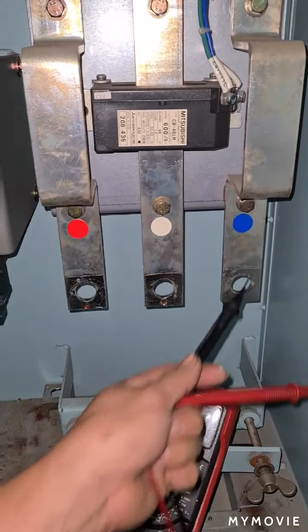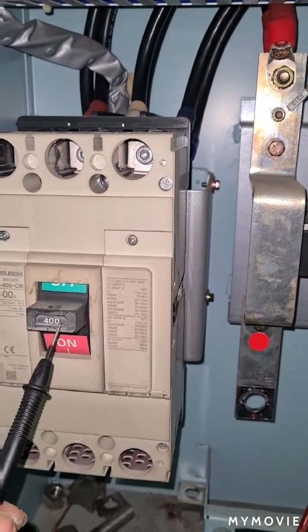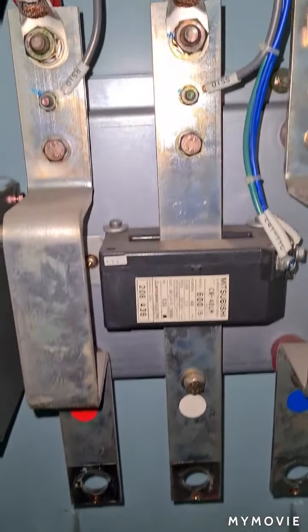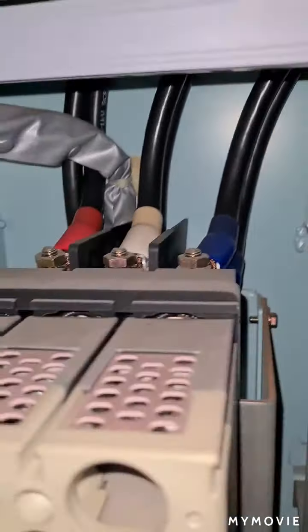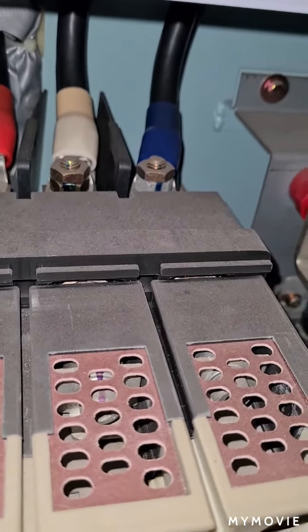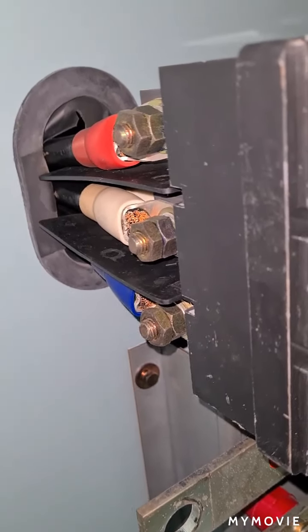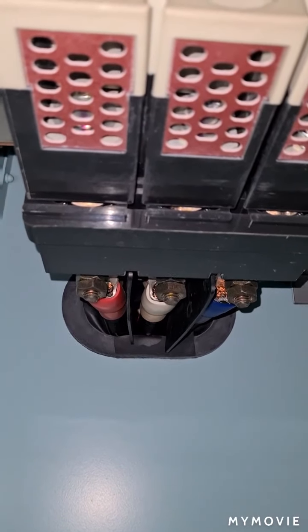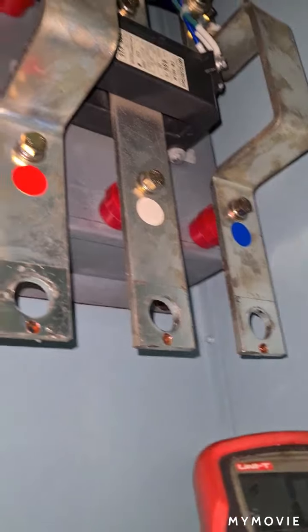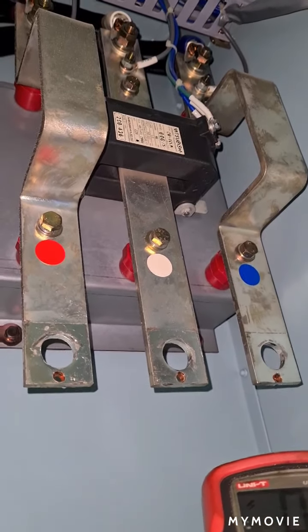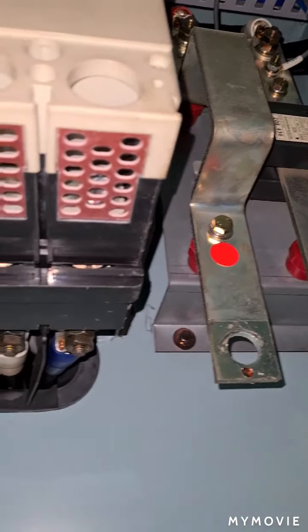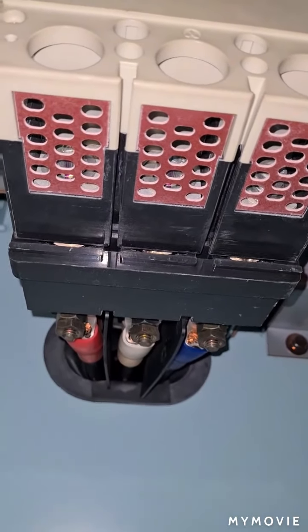Take note that this pole line 3 has no voltage. Put this switch off. As you can see here, we have a line going there, going inside, and this has the upper part portion, and this upper part portion is connected down. As you can see here, there is a circuit breaker connection down. This wire is live. Remember, be careful when you are going to make connection on this bus bar, because the distance of this bus bar going to the circuit breaker line are very near, so there is a possibility that you may get electrocuted on this portion.